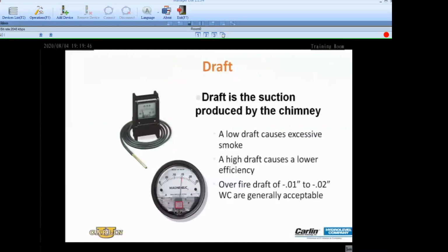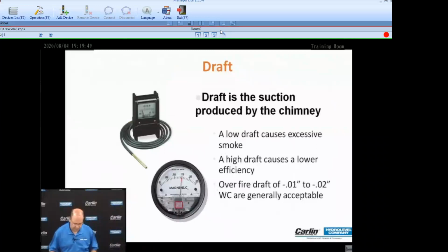Measuring draft. We all tell stories and hear jokes. Back in the day, you used a puff of smoke from your cigarette to measure the draft. If it got drawn up the chimney, yeah, good draft. If it took too long, well, maybe that wasn't such a good draft. You need a reliable gauge. You have to have a proper gauge to measure draft, and you have to know where to measure it.